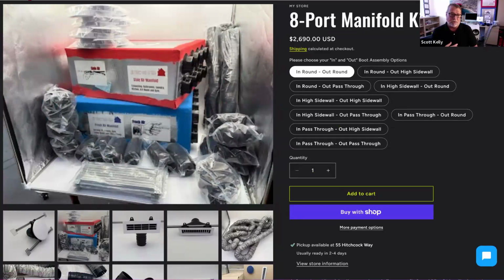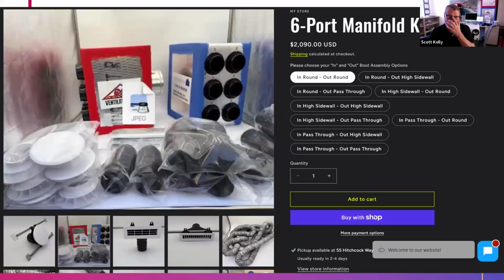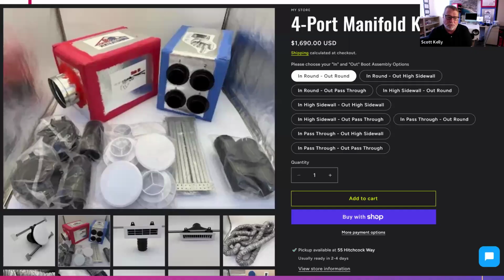You can see all the pieces and parts — everything you need to put these together. There's 4-port, 6-port, 8-port, 10-port. It's reasonable, $1,690 for the 4-port with all the tubing you need — under $2,000 for your whole ducting solution for an ERV. That's what was kind of missing in the marketplace, and that's how I landed on that approach.